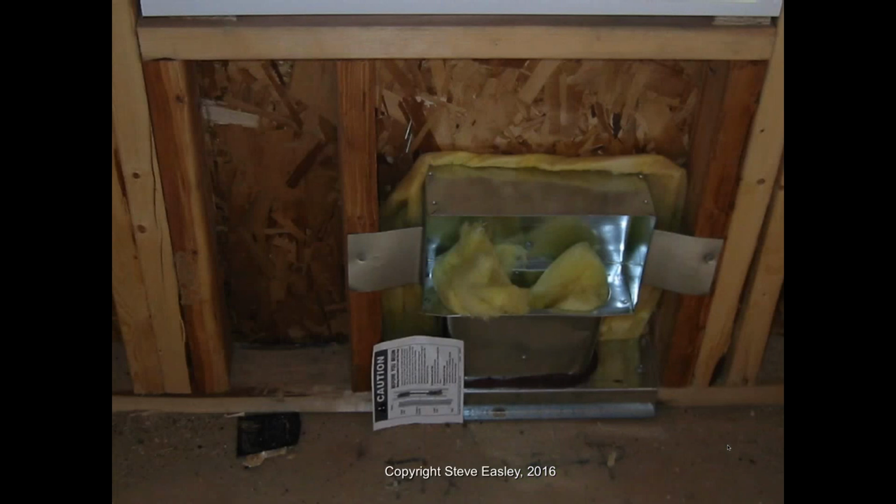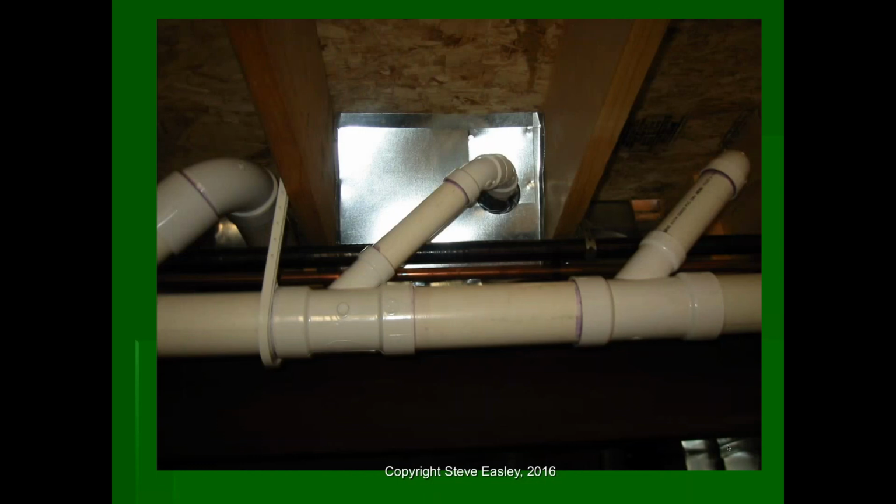We also never want to put ducts on exterior walls. The temperature differences are far greater than just the ambient temperature differences in the room. They're difficult to insulate and difficult to seal, and they create conditions where you get mold growing in the walls because of the duct leakage. You never want to do things like put soil lines inside of our ductwork. So even for return air ductwork, you can't use building cavities.